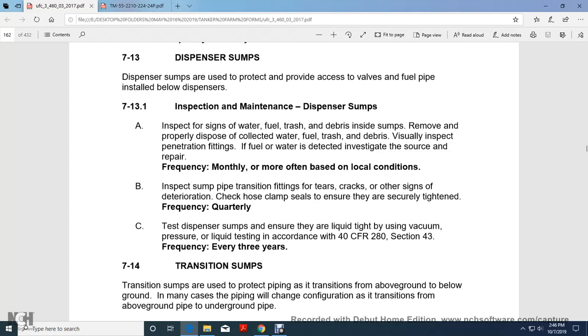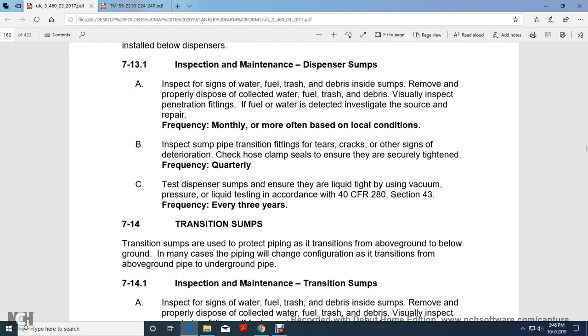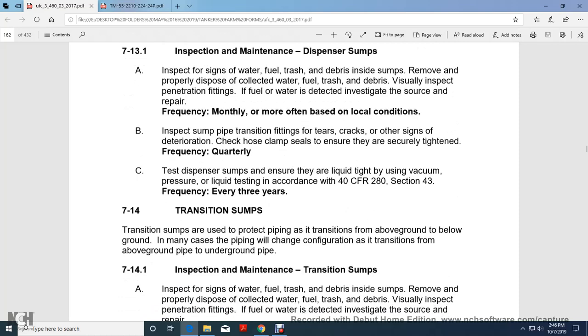Visually inspect the penetration fittings. If fuel or water is detected, investigate the source and repair, monthly or more often based on local conditions. Inspect the sump, pump, sump pipe, transition fittings for tears, cracks, and other signs of deterioration. Check the hose clamp seals. Ensure they are securely tightened, quarterly.